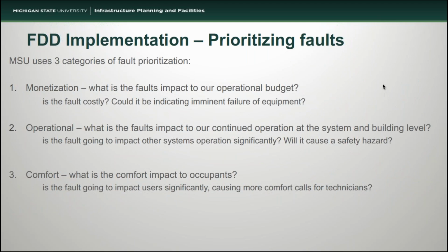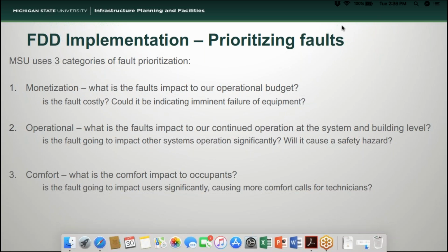So once we've detected a fault, we really need to categorize it into one of 3 types of faults. We use primarily monetization. So what is the cost of this fault happening? Is it something that's costing a lot of money, or is it something that really could be pointing out a significant chance of an imminent failure? But there are faults that will be detected that aren't necessarily going to save you money. Maybe it's a fault where we're below the heating set point, and what needs to happen is we need to open the heating more. Well, that's going to cost us money, but it is an operational fault. So we also need to look at how is this fault going to impact other systems? Or in the case of not providing ventilation, could it possibly be a safety hazard?